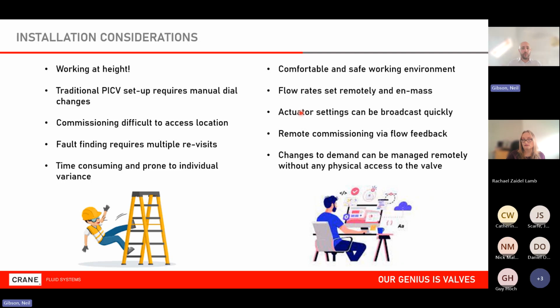All of these are installed and they don't realize that until they're up in the ceiling void, which requires someone to go up, take the lid off the actuator and change the dip switch. But now if I discover that, I can access the required register and I can send the new value to all of them and fix that issue within seconds, rather than days of someone going up and down ladders and getting in the way of someone else trying to do other commissioning and setup in that space. So we can reduce some of that burden that's currently experienced.